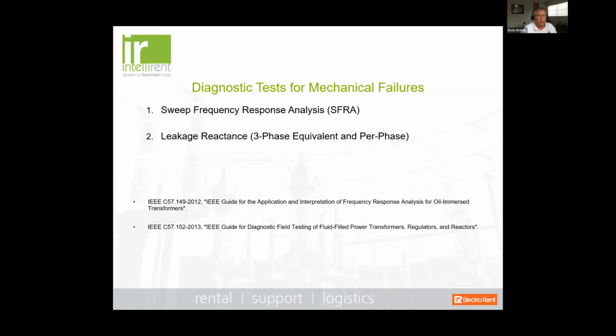The two different types of tests that we run to determine mechanical failure on larger oil-filled transformers are your sweep frequency response analysis, your SFRA, and also your leakage reactance, both three-phase equivalent and per phase. And again, if you need guidance on these types of tests, there is IEEE C57.149, which is a guide for the application and interpretation of frequency response analysis for oil-filled transformers. This is currently in revision, and hopefully by the next Transformers Committee meeting this fall, we will have approval and get it published. But all it did was extend some of the information available for this type of test. And then C57.152, the guide for diagnostic field testing of transformers, regulators, and reactors, is also available to talk more about the leakage reactance tests.